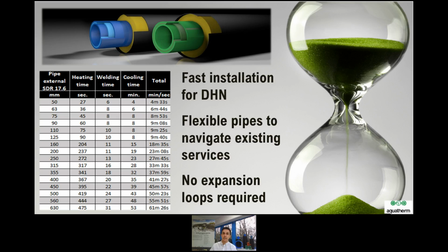In addition, expansion provisions such as expansion loops and foam pads are not required with Aquatherm pipes due to the low expansion force of polypropylene. This enables the pipe system to absorb expansion forces when buried without detrimental effects on the service life of the pipework. This leads to a saving of material cost, the cost of civils, and reduces the disruption to residents and businesses, which can be caused when roads and pavements are closed.